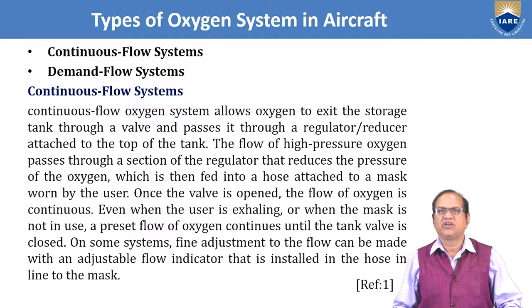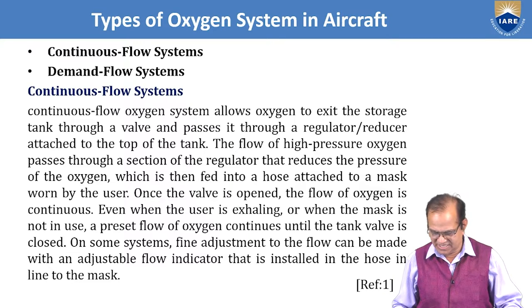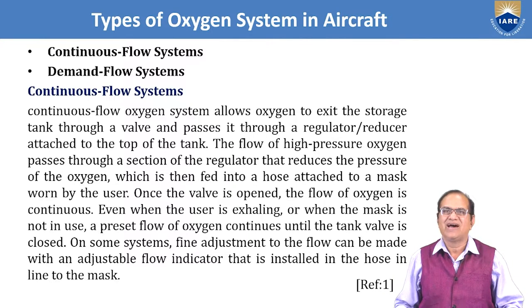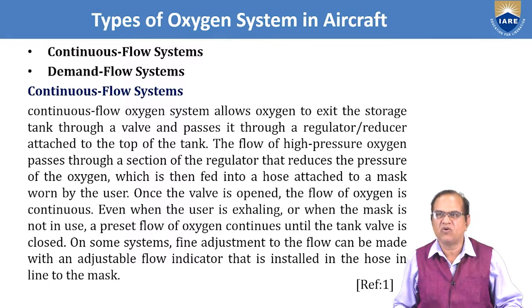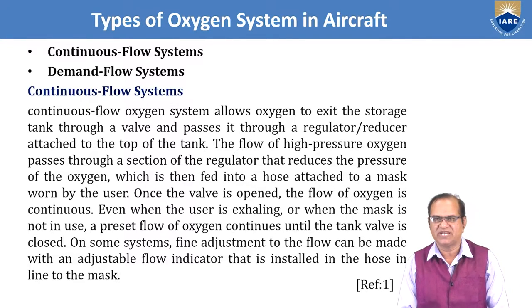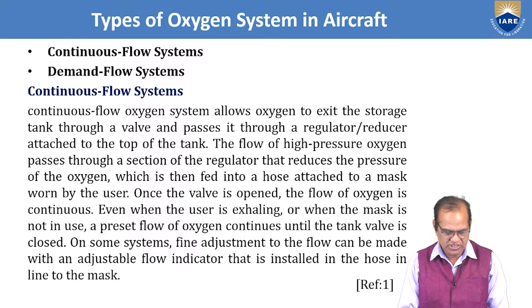The flow of high pressure oxygen passes through a section of the regulator that reduces the pressure of the oxygen, which is then fed into the hose attached to the mask worn by the user. Once the valve is opened, the flow of oxygen is continuous, even when the user is exhaling or when the mask is closed. On some systems, fine adjustment to the flow can be made with an adjustable flow indicator installed in the line to the mask.